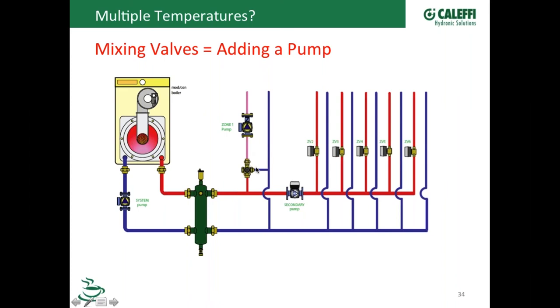I mean, among other things, if the mixing valve starts to close down the hot inlet port, you're going to also reduce flow through the rest of your zone. You're going to deadhead your circulator and everything else. By pulling through the mixing valve, you're going to create an equal pressure at both the hot and cold inlets, so that way the mixing valve can operate appropriately.